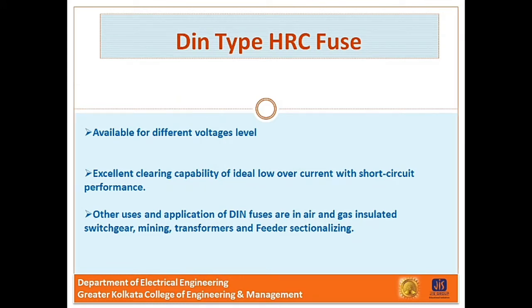Next one is DIN type HRC fuses. Now DIN type fuses are available in wide range of rated currents. DIN fuses are used for different purpose with their characteristics at different temperature condition. And these types of fuses are available for different voltage level and can be used in transformer protection and even where there is no low voltage secondary or backup protection. They have excellent clearing capability of ideal low overcurrent with short circuit performances. And the other uses and application of DIN fuses are in air and gas insulated switchgear, mining, transformer, feeder sectionalizing.